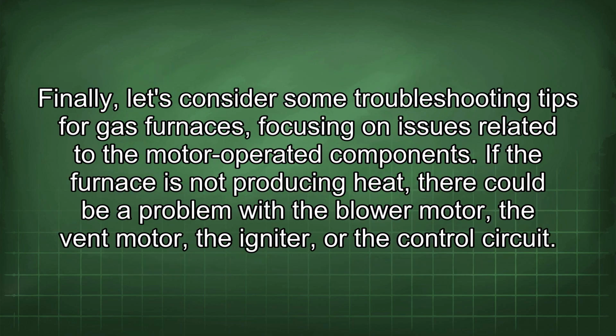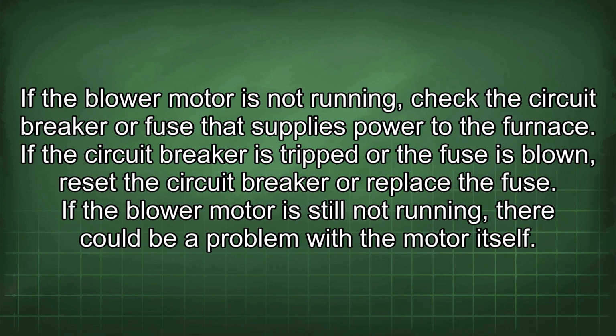Finally, let's consider some troubleshooting tips for gas furnaces, focusing on issues related to the motor-operated components. If the furnace is not producing heat, there could be a problem with the blower motor, the vent motor, the igniter, or the control circuit. If the blower motor is not running, check the circuit breaker or fuse that supplies power to the furnace. If the circuit breaker is tripped or the fuse is blown, reset the circuit breaker or replace the fuse.